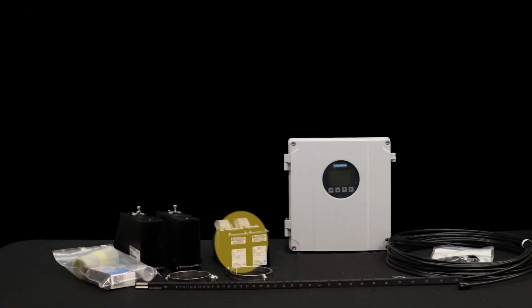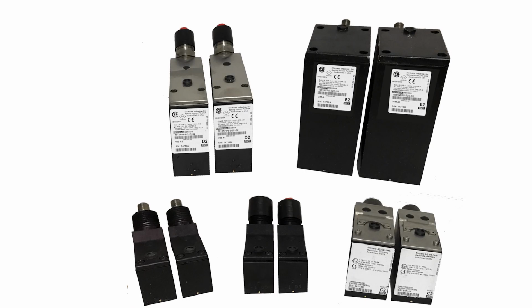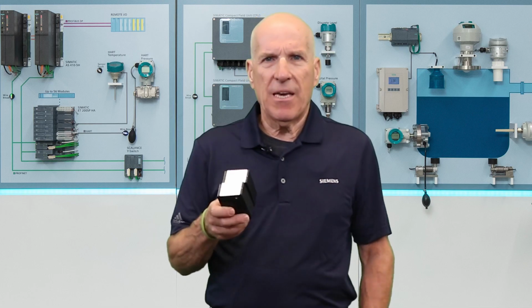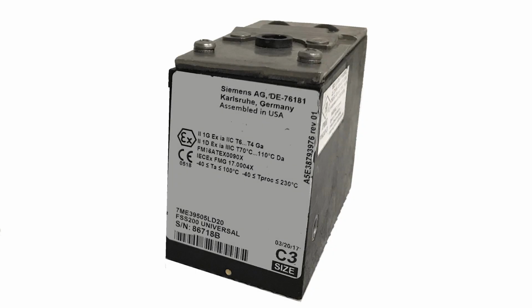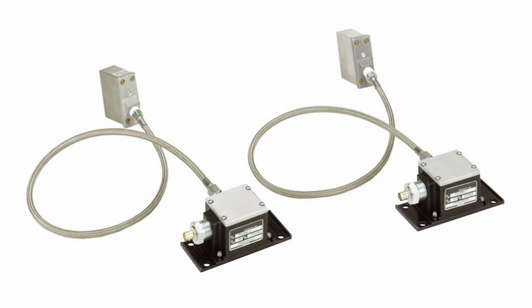While the high precision sensors that we just looked at are specifically for steel pipe, if your pipe is not steel, you'll receive universal sensors appropriate for the diameter range specified in your order. For example, here is a set of C3 universal sensors that could be identified by their label. If your application operates at temperatures above 250 F or 121 C, you'll receive high temperature sensors. These are all metal construction and suitable for temperatures up to 450 F or 230 C. They are identified by a part number size 1 through 4, shown on their labels, which appears on the junction box attached to the sensors.